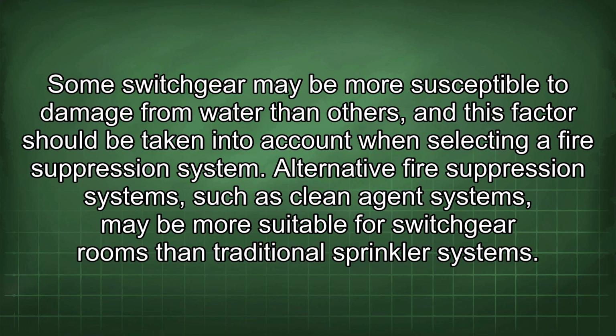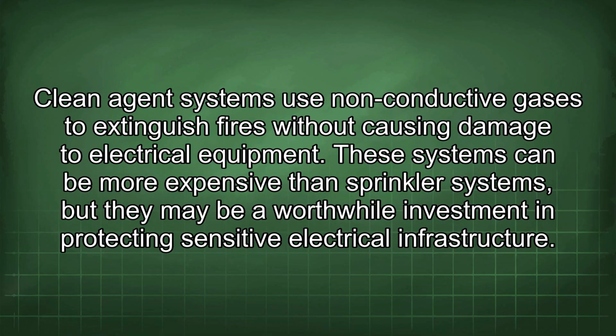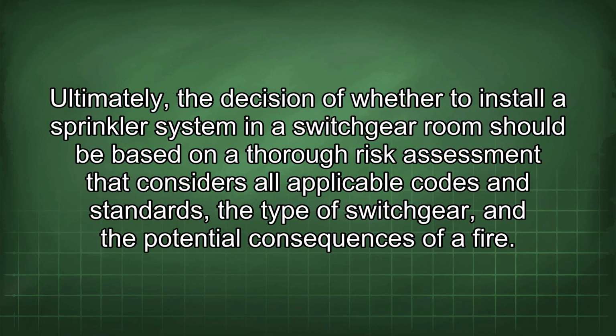Alternative fire suppression systems, such as clean agent systems, may be more suitable for switchgear rooms than traditional sprinkler systems. Clean agent systems use non-conductive gases to extinguish fires without causing damage to electrical equipment. These systems can be more expensive than sprinkler systems, but they may be a worthwhile investment in protecting sensitive electrical infrastructure.